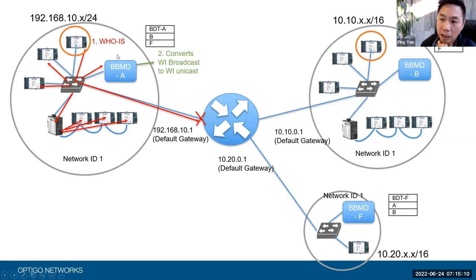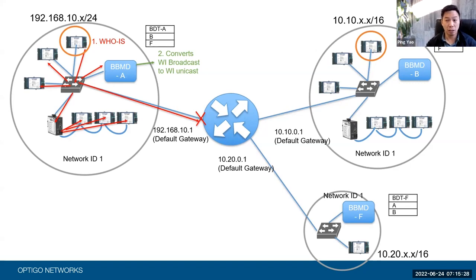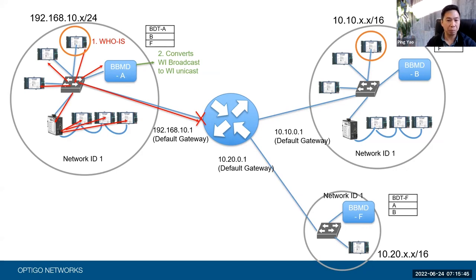BBMD-A sees that this BACnet broadcast message reached it and goes: I've got to do my job. I'm going to take this BACnet broadcast message and convert it into a unicast message. Now, where do I send it? Because if it's unicast, you have to send it directly to a certain place. So it's going to go through its BDT — its broadcast distribution table — and say: who do I send it to? In its BDT, it has B and F. B will be the IP address of BBMD-B, and F will be the IP address of BBMD-F.